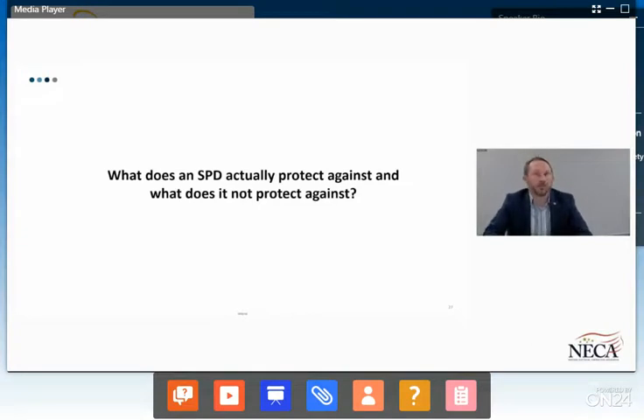Well, it's real simple — SPDs protect against transient voltage. There's some filtering capability in some devices, but ultimately you're purchasing an SPD to protect against transient overvoltage. It doesn't protect against temporary overvoltage, sags, or swells. But here's a key thing a lot of people miss: the vast majority of other power quality incidents have an associated transient voltage with them. If you get a sag in your system, you're going to have a transient voltage event associated with that sag.